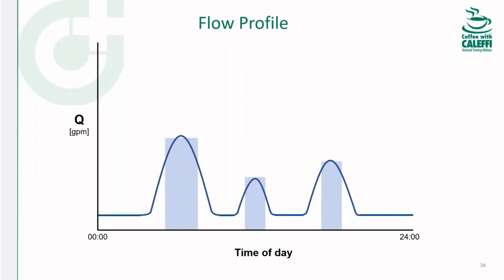What's very typical of a domestic water supply application is that we spend a high amount of time at the low flow hours. In reality, booster systems are only at an appreciable flow rate for around 4 to 6 hours a day, which is the blue boxes. That means 18 to 20 hours every day are spent at very low flows, which is the green shaded areas. This is what we mean by flow profiles: how much time is spent at what flow rate. Obviously different flow profiles exist for various applications. An office building might look a little similar, but you'll have more activity in the middle of the day and even less at night. An industrial application, like a washdown, would probably match the shifts and things of that nature.